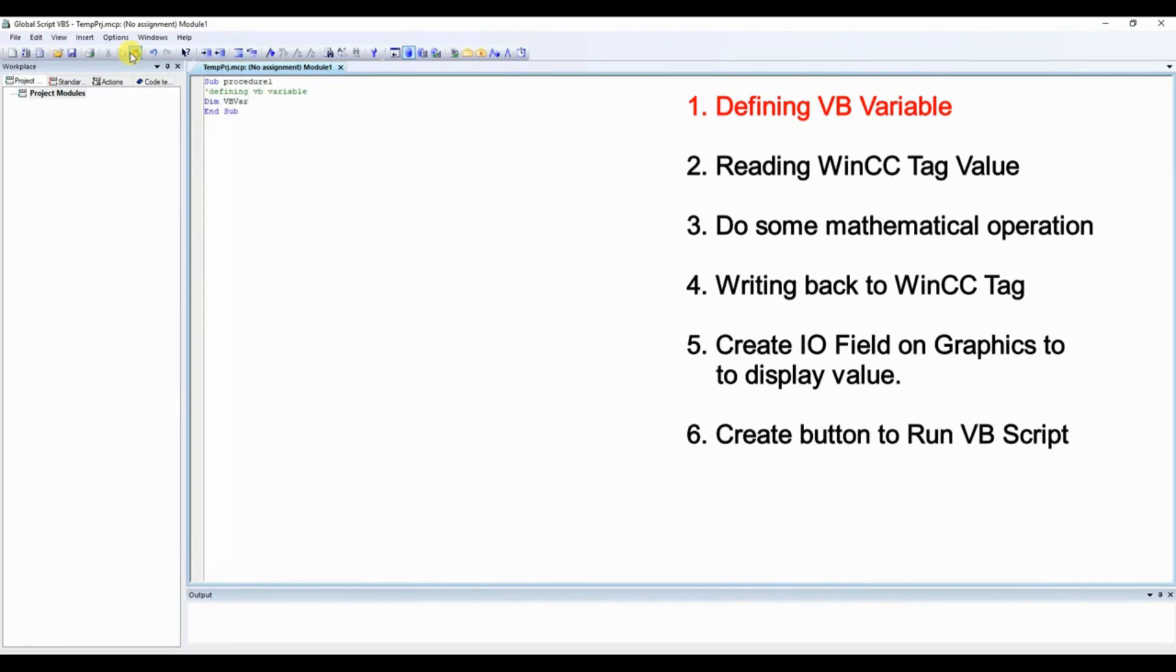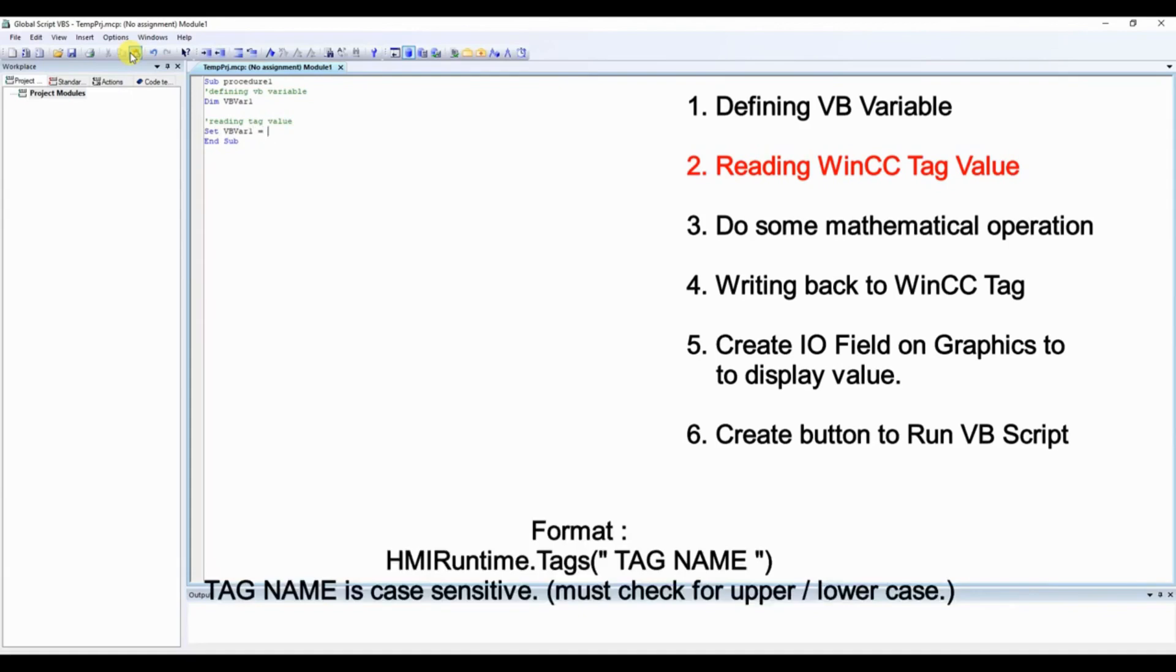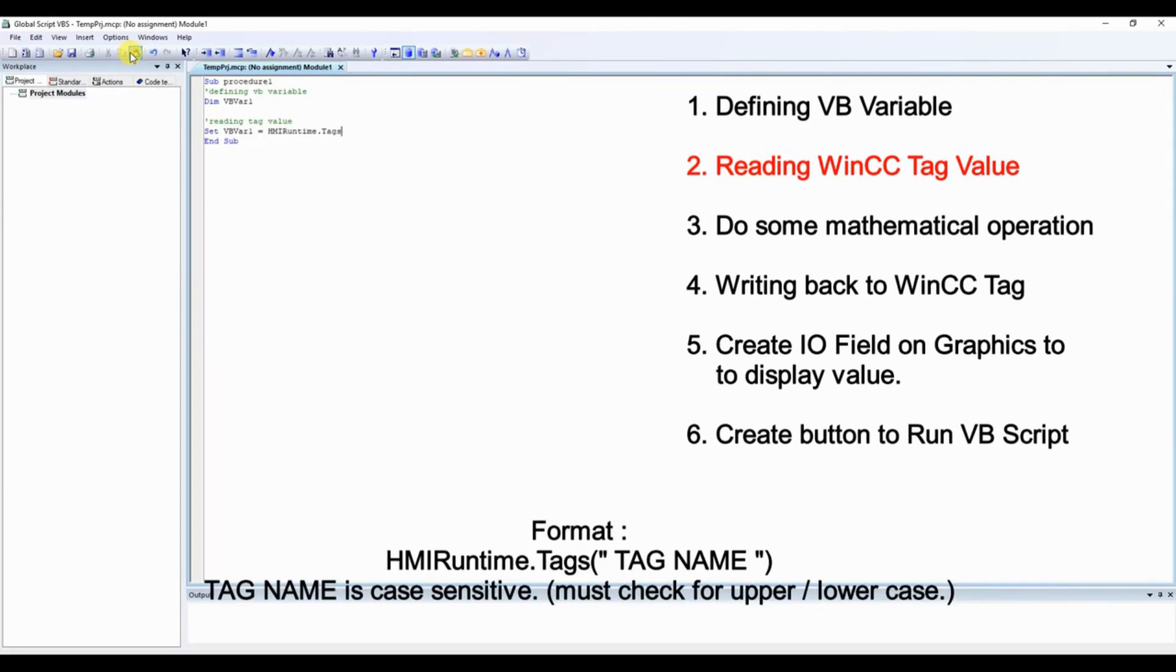Now here define a variable with name VBVar1. To read the WinCC tag into this variable we will use the hmiruntime.tags instruction. Set the value of VBVar1 variable equal to hmiruntime.tags, and in bracket the tag which we need to read. Here our tag is tag_1.